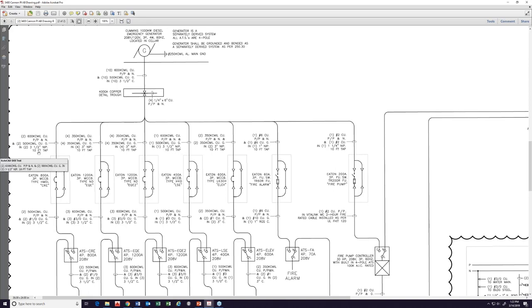So we're taking a 10-foot tap rule and tapping into an 800-amp device. And that 800-amp device is going to feed an 800-amp ATS, an automatic transfer switch, to feed specific types of loads. And there are a couple of things that I'm achieving here. Number one, I'm saving money by removing that big breaker. This is a megawatt. I would have needed a huge breaker that would have cost the customer probably $10,000 to $20,000. I'm removing that, and I'm eliminating the issue with selective coordination that it would have had to feed. Because remember, a couple of these devices are actually 1,200 amps. They're pretty big. And I would have a hard time selectively coordinating them, especially because when there is a fault, the available current is pretty low and they get difficult to selectively coordinate.